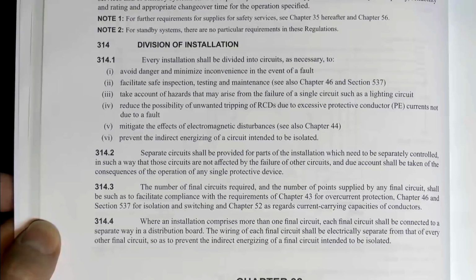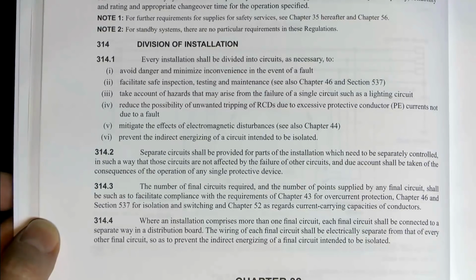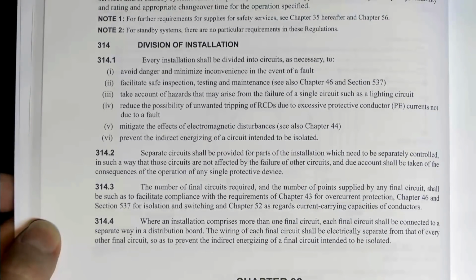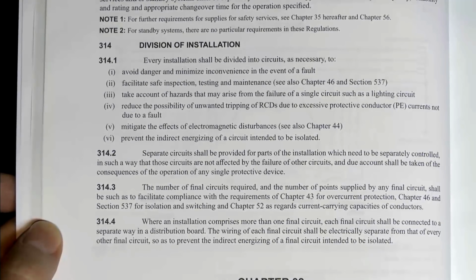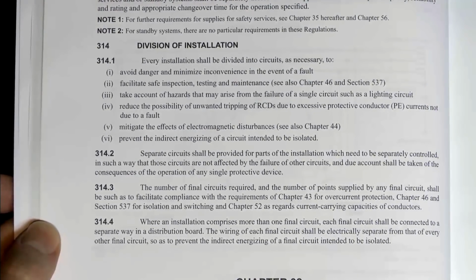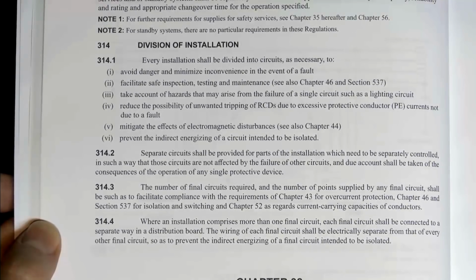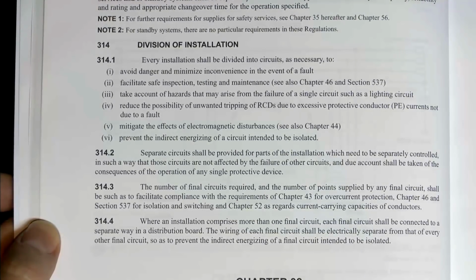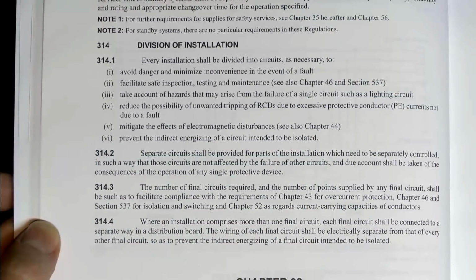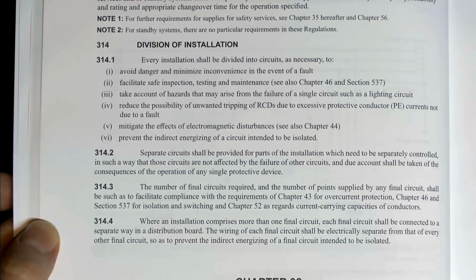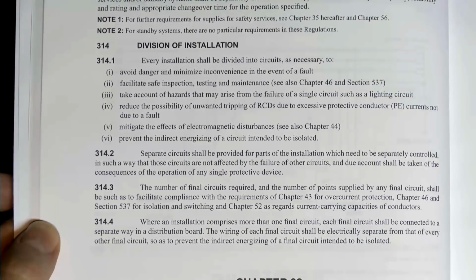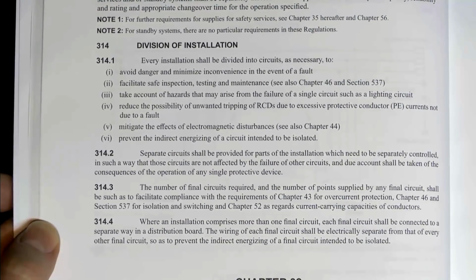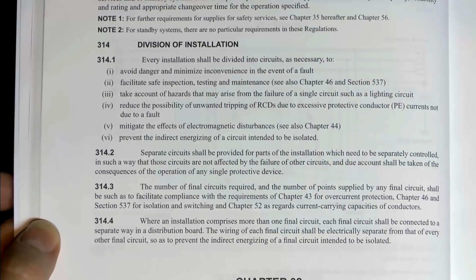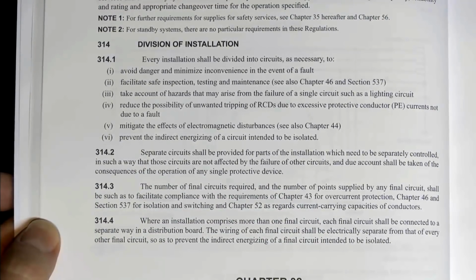So the reality is that consumer units with two RCDs splitting it into halves aren't complying with this, and haven't been compliant for many, many years. The proper answer is to fit RCBOs, one per circuit, so you are complying with this - it's divided into circuits and minimises inconvenience because one circuit doesn't affect any of the others. This isn't particularly new, but as we'll see in later videos, it's been reinforced elsewhere, so dual RCD consumer units are not compliant and in reality haven't been for many years. If we're thinking of fitting those, think again - really, it's time for those to go away permanently.